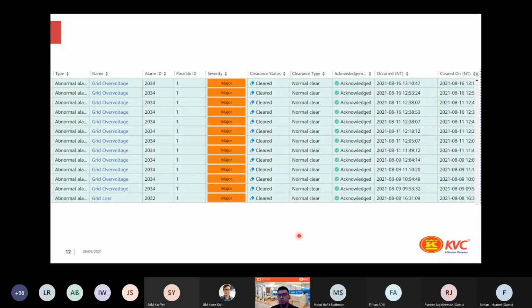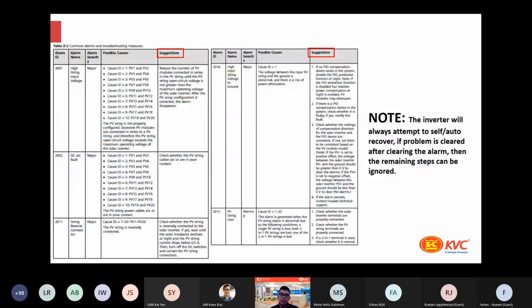So what is the problem here? It's due to grid over voltage. This is a more common alarm that we usually face. But look at this slide, you'll see that although it's grid over voltage, the alarm occurred on, for example, 16th of August, but at the same time it was also cleared. That explains why the inverter has already cleared the alarm, why the inverter can turn back on, and why you see the intermittent on and off of the inverter. So always when you look at the alarm, look at the alarm ID. Once you have the alarm ID, flip into the manual, search for what that alarm ID means, and look at the suggested method.